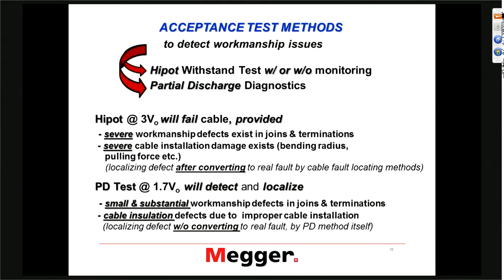There is some knowledge that once you pass a hypot test, you can typically expect maybe a two- or three-year period without any trouble on the cable, but there are situations where that assumption is incorrect. That's where, if we do not just a plain hypot test but a monitored withstand test — where we monitor certain parameters — then we can see during the duration of the test whether this cable is going to fail or not.